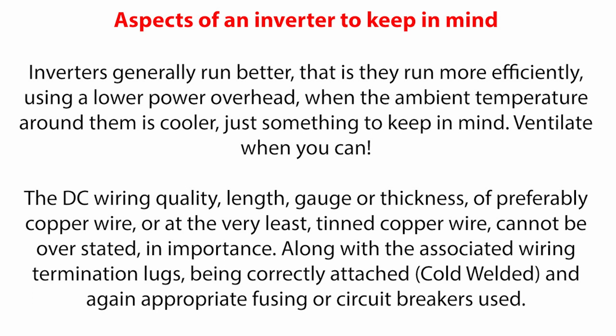One of the most important considerations to make and apply when installing an inverter is the gauge or thickness of the electric wiring being used. This is very important, certainly on the DC battery side of the configuration. Please watch my number 5 electric wiring tutorial, as the gauge of thickness and the length of the wire being used to connect the inverter to the battery cannot be stressed anymore as to their importance for both the correct functioning of the inverter and ultimately for safety. Thick gauge wires and the shorter the run of wire to the battery is generally the best setup.